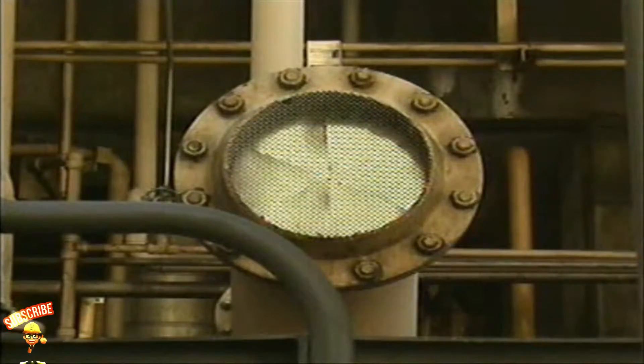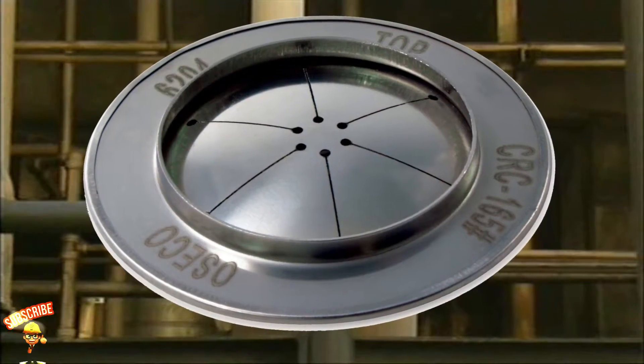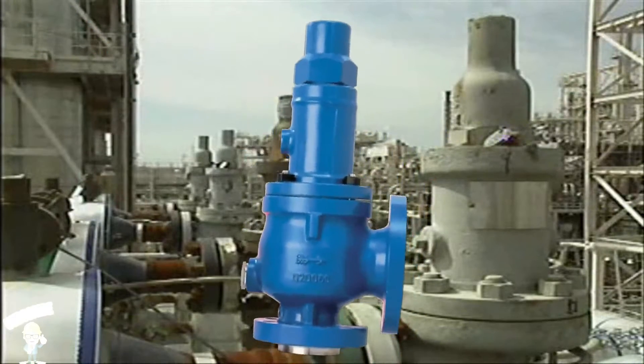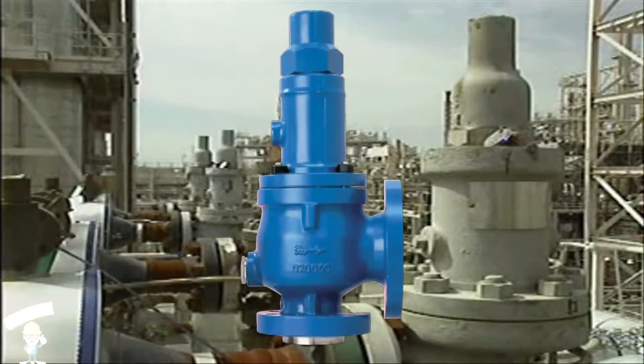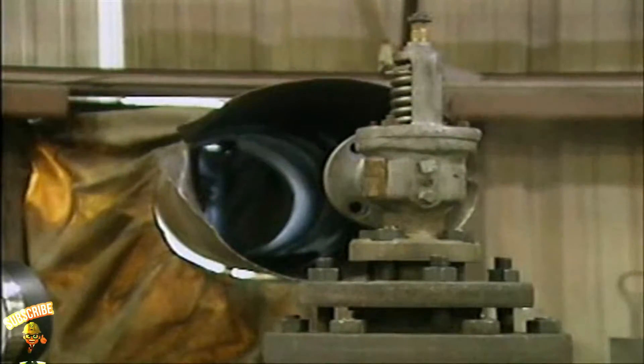Rupture discs are often used in systems where problems with excess pressure are relatively unlikely. Relief valves, which open gradually, are primarily used in systems that handle pressurized liquids. In gas or steam systems, however, safety valves are used.